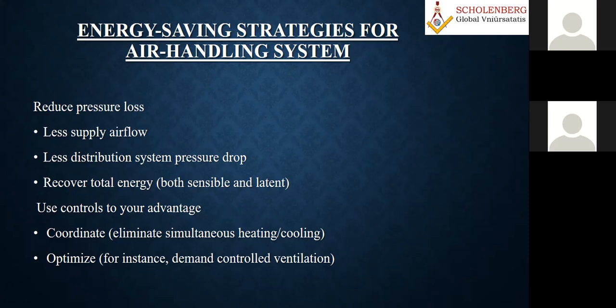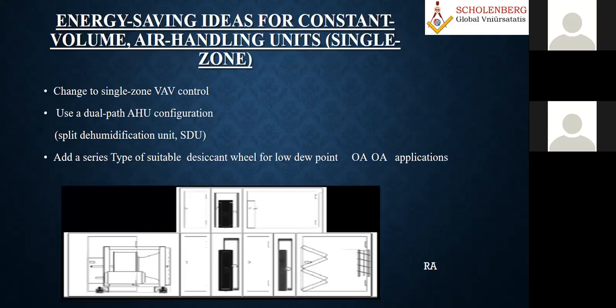Otherwise, most of these electronic controls or sensors have a life cycle of only 2 to 3 years. And then it starts malfunctioning, it does not sense properly, and it does not give the analog signal correctly. And if you have some issue with updating your digital data controller, then whatever the system you are operating, the energy you are trying to save, everything will become useless. So these are all the various things you can go for.